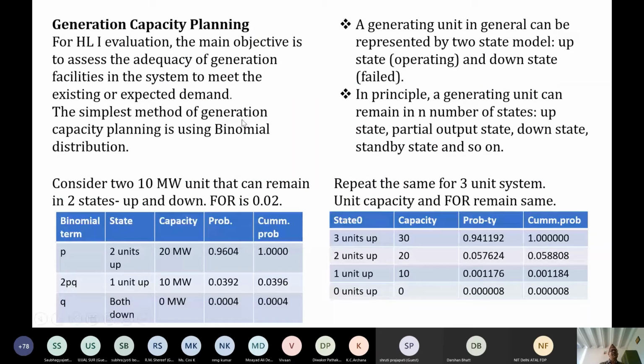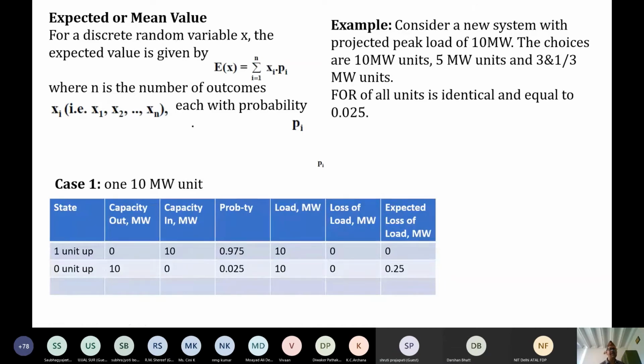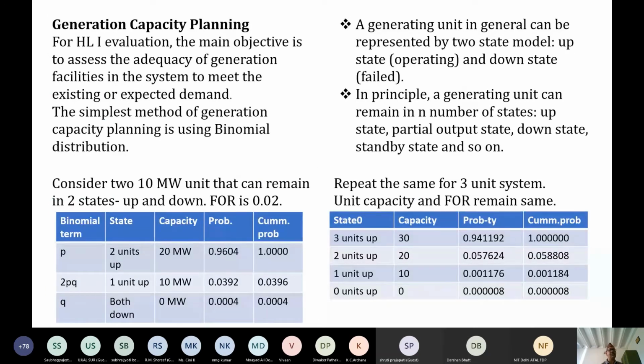So generation capacity planning. How do we plan generation capacity? For HL1 evaluation, the main objective is to assess the adequacy of generation facilities in the system to meet the existing or expected demand. Existing or expected demand means if it is the existing system, then existing demand. If it is a new system, then it is expected demand. The simplest method of generation capacity planning is using binomial distribution. A generating unit in general can be represented by a two state model: up state, operating, and down state, fail.